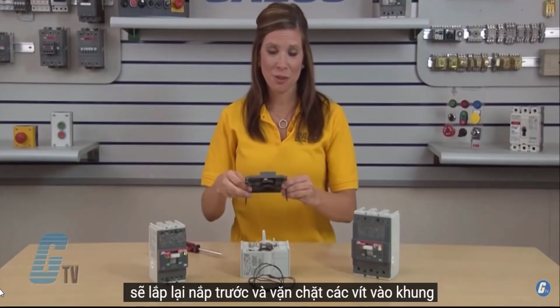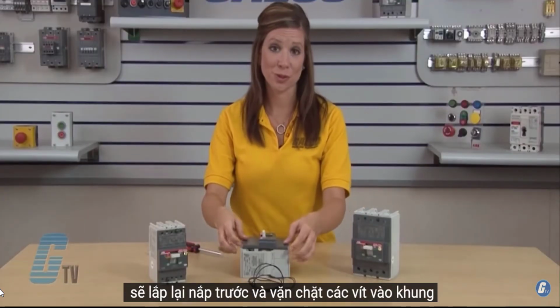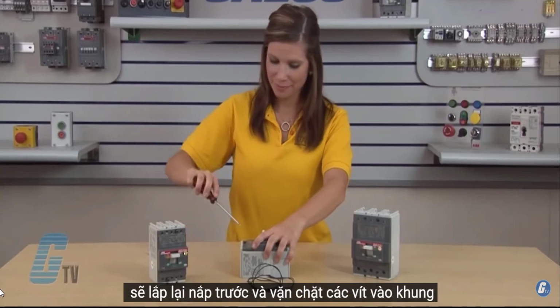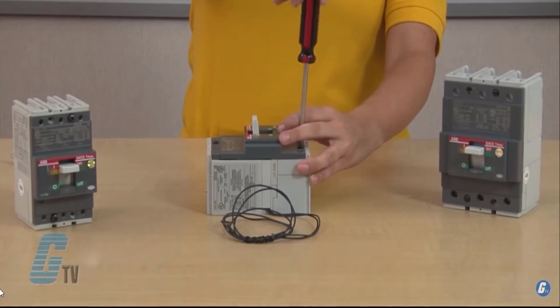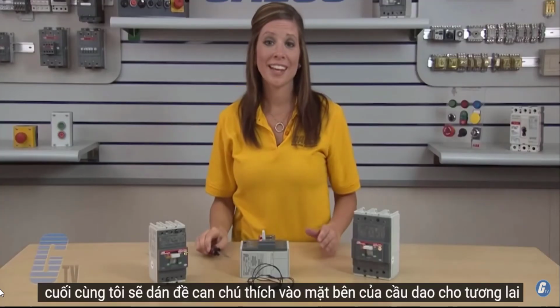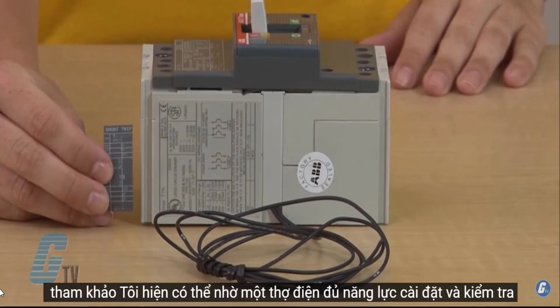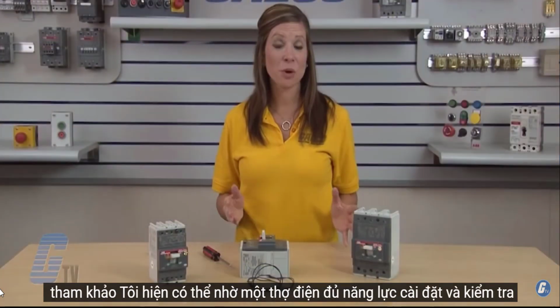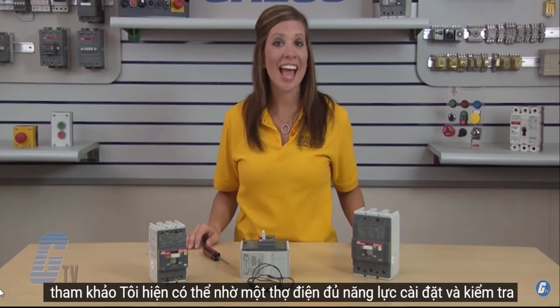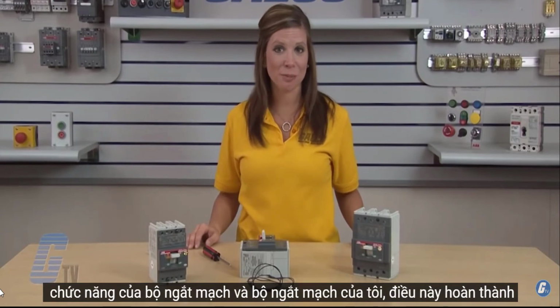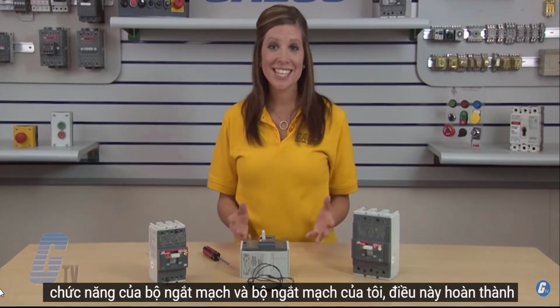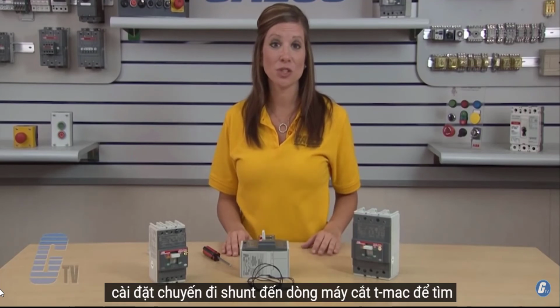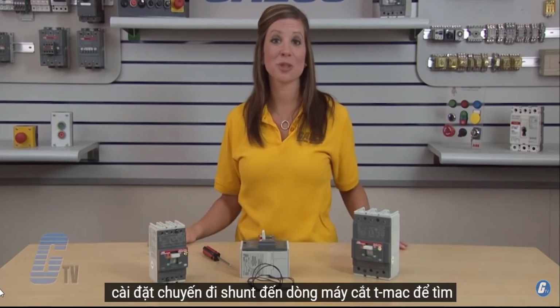Now I will reinstall the front cover and fasten the screws to the frame. Finally, I will apply the legend details on the side of the breaker for future reference. I can now have a qualified electrician install and test the functionality of my circuit breaker and shunt trip unit. This completes the installation of the shunt trip to the TMAX series of circuit breakers.